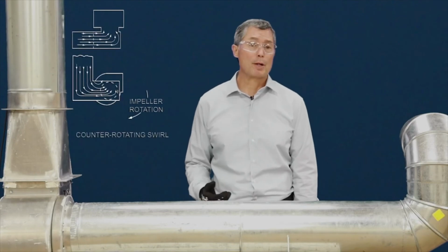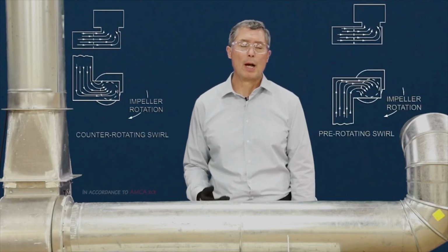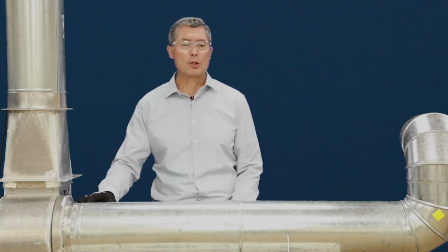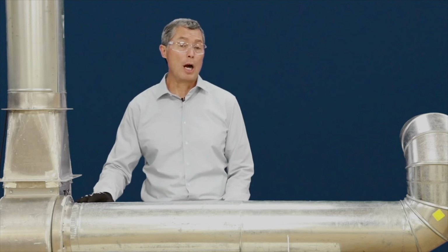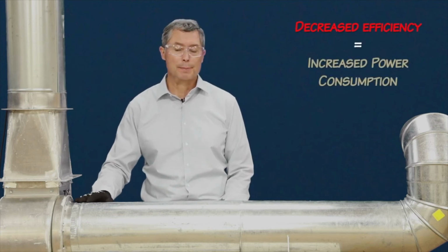Final thoughts on corkscrews. As you can see, corkscrew ductwork does affect the way a fan performs. If you counterspin the air, you'll have much better performance than if you pre-spin the air. However, with counterspinning the air, we just have to make sure that we compensate for that with a little bit of a safety factor on energy consumption, because we are going to consume more energy.